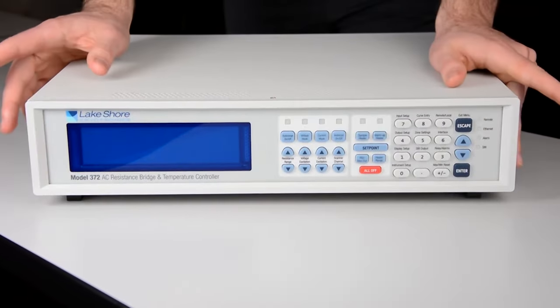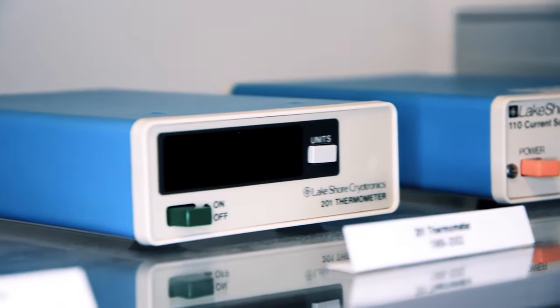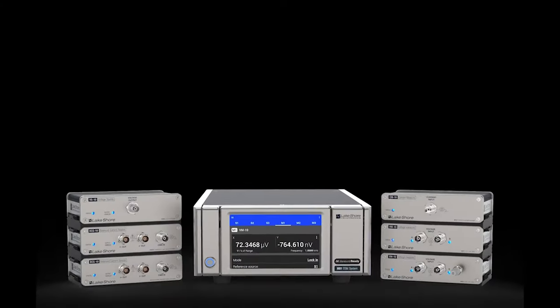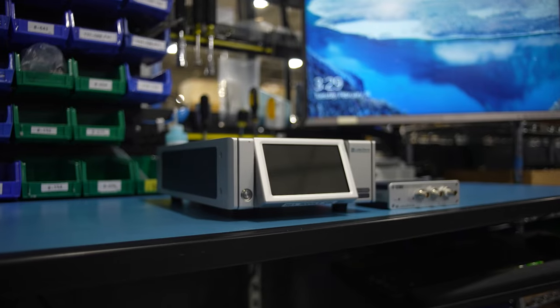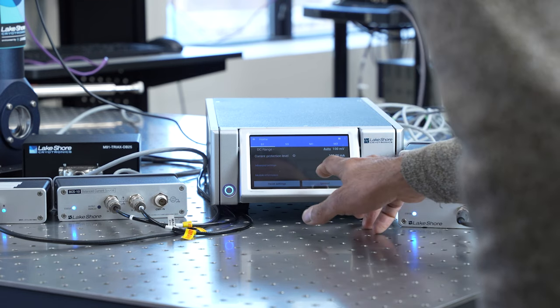Lakeshore has a long history in making low-level measurements of temperature in cryostats and other cryogenic equipment. Those sensor applications and measurements require very low noise, very sensitive circuitry, which was used in the design and development of the M81 to enable a more general purpose solution optimized for best possible noise performance for cryogenic and other low-level applications. The M81 is an all-in-one solution combining very high quality sourcing, measuring, and lock-in detection in a compact, convenient package that is modular and supports up to six channels of sourcing and measuring.